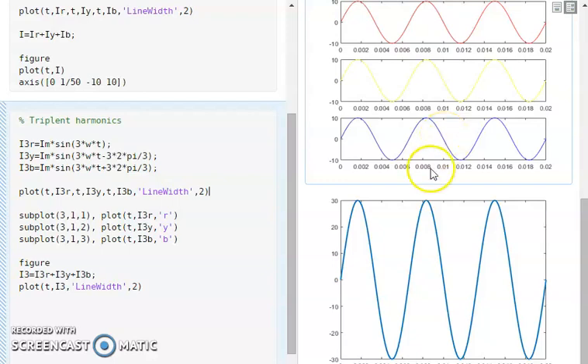So what will happen when I add all the three together and plot it? Here you can see that when I add all the three triplet harmonics together, the net component is three times more than any of the triplet components in R, Y, or B phases. That means the neutral current becomes overloaded.